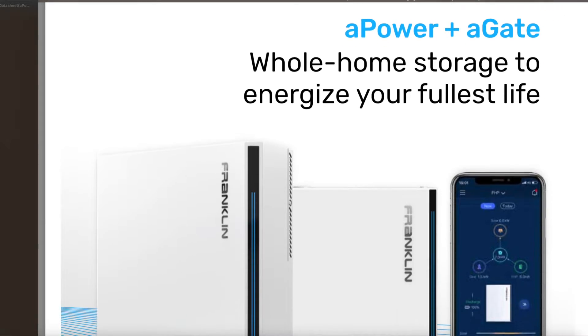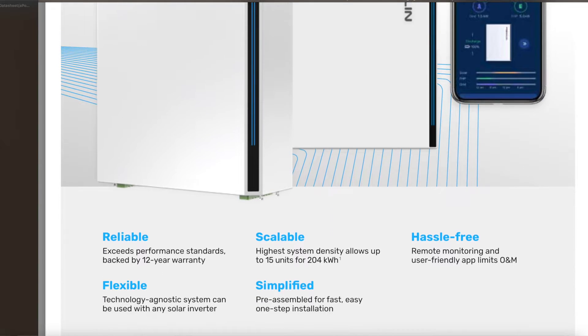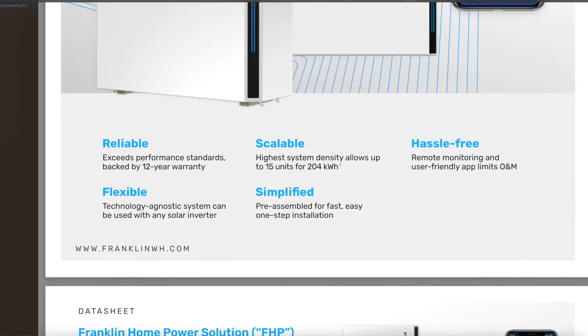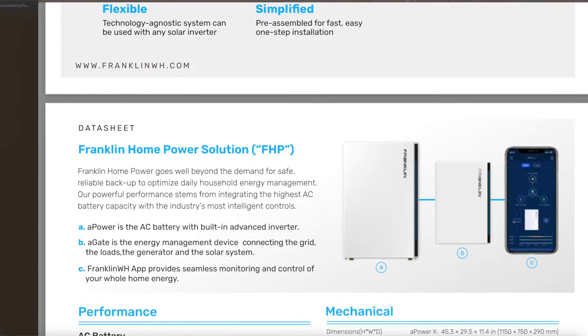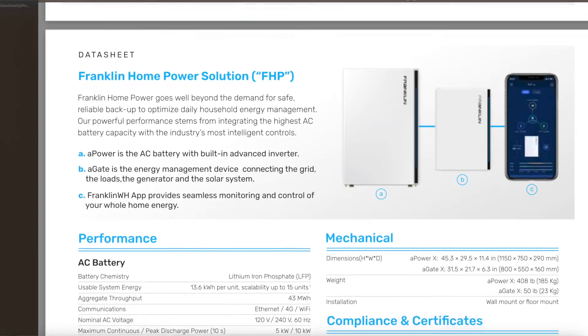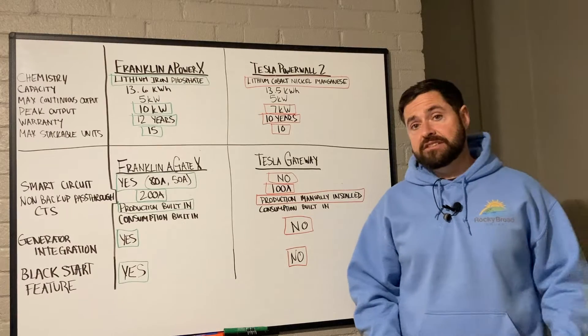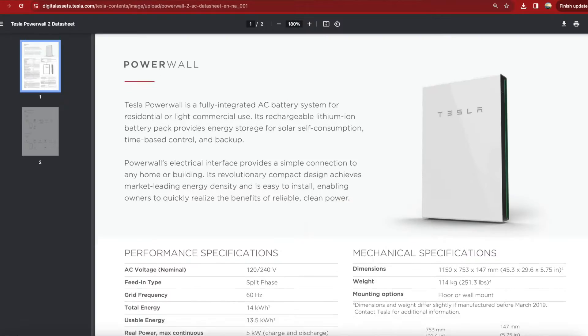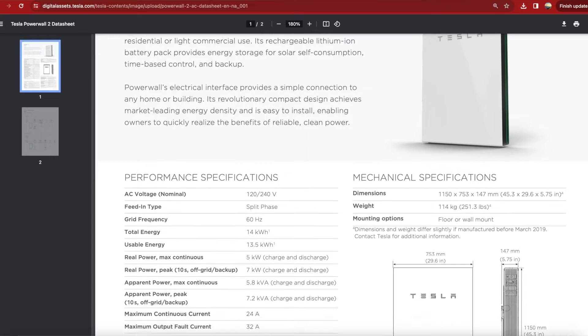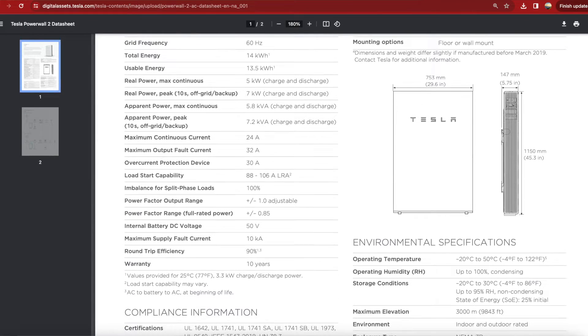The APower X is a lithium iron phosphate battery — that is the newer technology. It's more reliable and less prone to thermal runaway. The Tesla Powerwall 2 is still operating on lithium cobalt nickel manganese, otherwise known as lithium-ion.